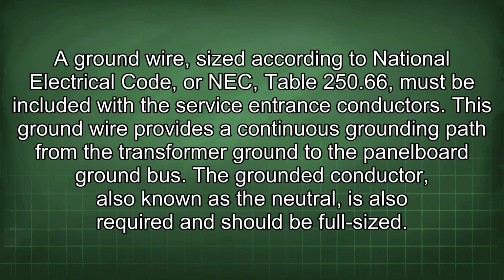A ground wire, sized according to National Electrical Code, or NEC Table 250.66, must be included with the service entrance conductors. This ground wire provides a continuous grounding path from the transformer ground to the panelboard ground bus. The grounded conductor, also known as the neutral, is also required and should be full-sized.